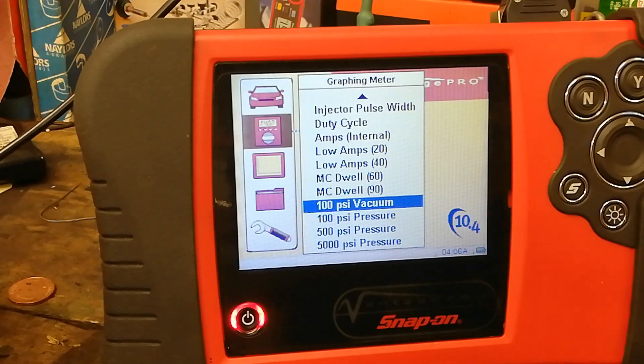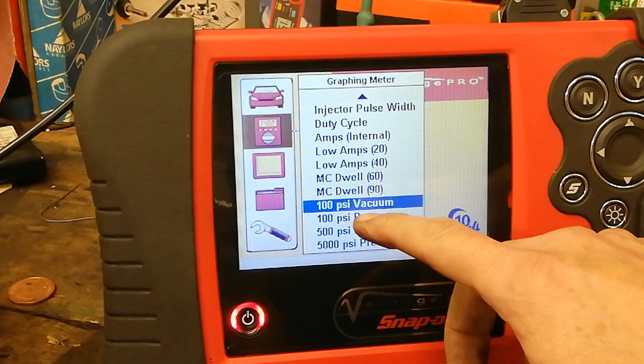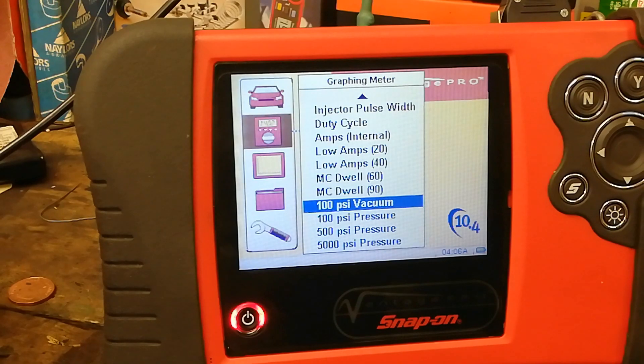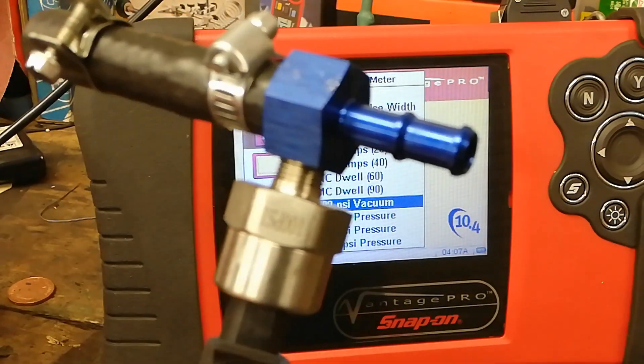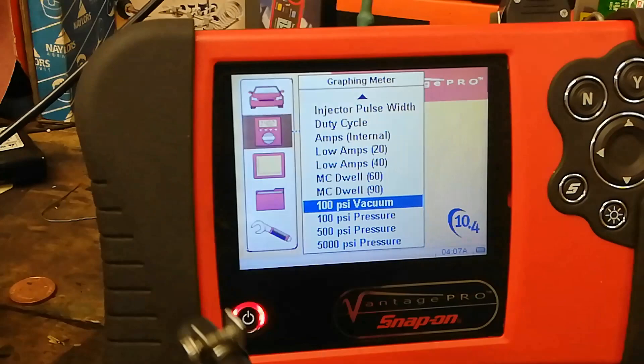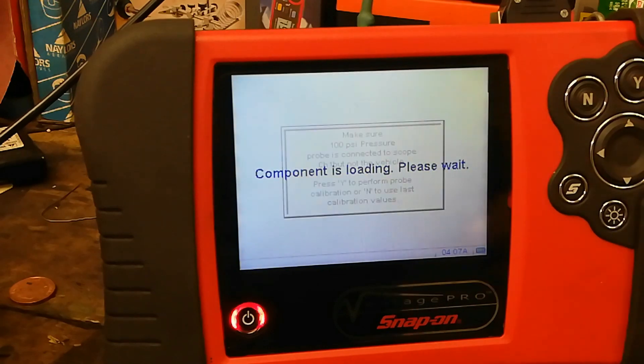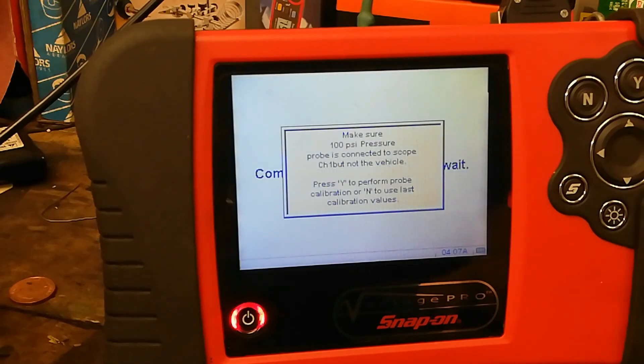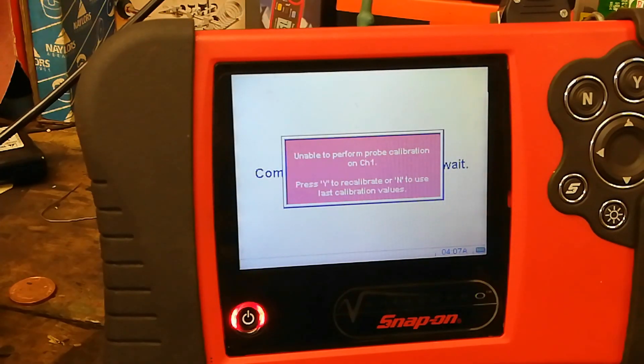Back on the wee Vantage again - is this any use to us? With the 100 PSI range and the 100 PSI pressure transducer, it doesn't calibrate at all. With it connected to the Vantage and set to 100 PSI pressure - component is loading, it wants to calibrate - yes - unable to perform calibration.